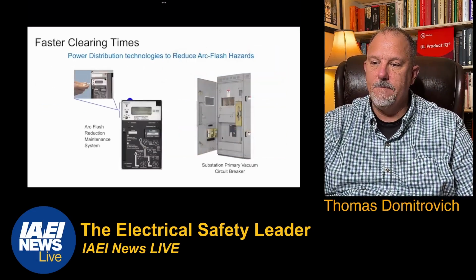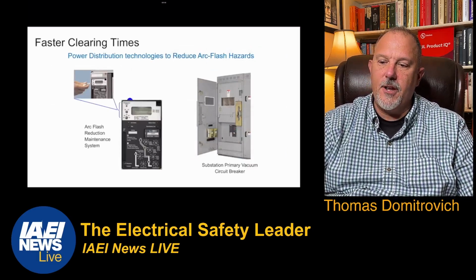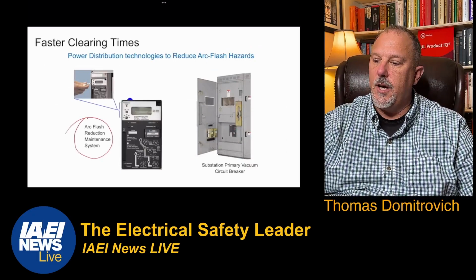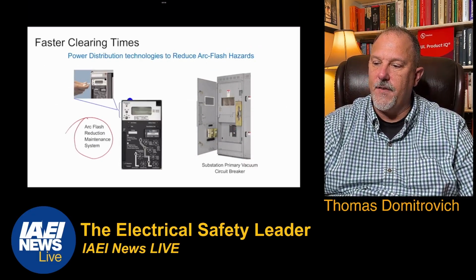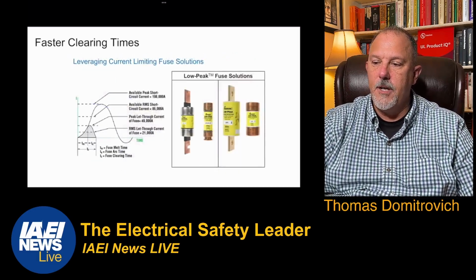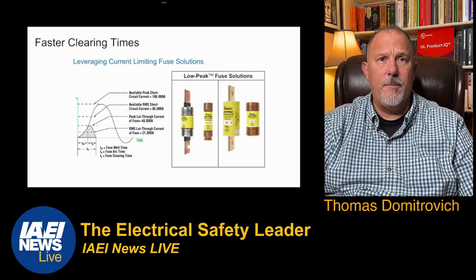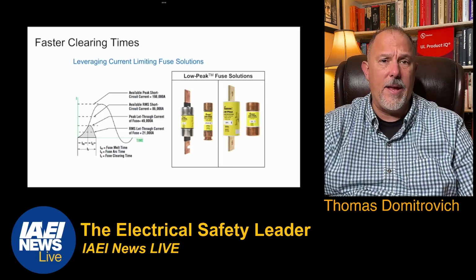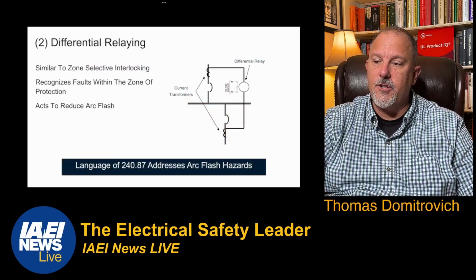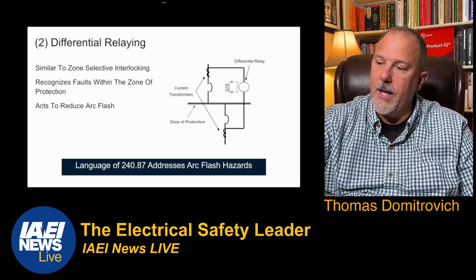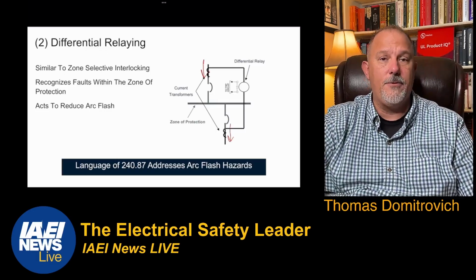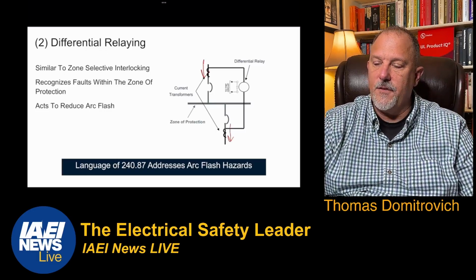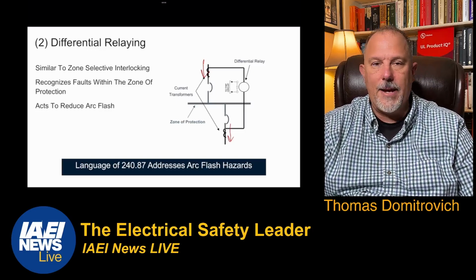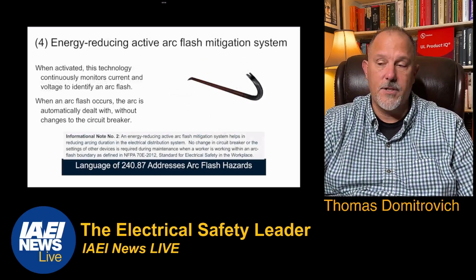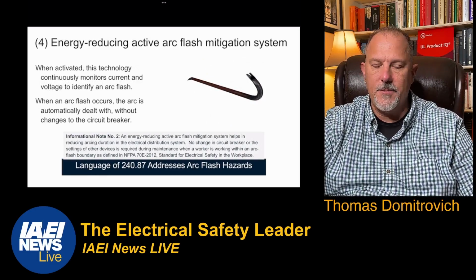Move people further away. We can reduce incident energy: the arc flash reduction maintenance system, substation primary vacuum circuit breakers. You could have, again, arc reduction technologies. Current limiting devices like fuses are one of the most efficient devices that we have out there to clear fault currents. Differential relaying. Remember, in the zone of differential relaying, the gazintas have to equal the gazaltas. If there is any difference, if you have more current going in and less current going out, it will trip. And vice versa. The crowbar active arc flash mitigation systems, these quenching technologies, are phenomenal for what they can get done.